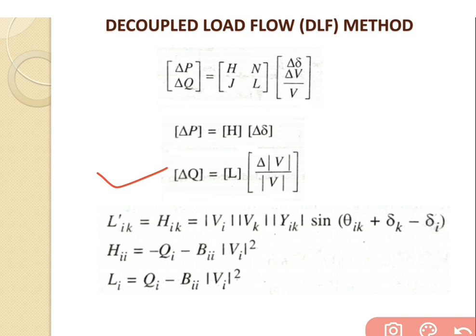The equation for power studies using Newton-Raphson method, which we have already obtained, is written as delta P and delta Q equals H, N, J, L into delta delta and delta V by V. The fast decoupled load flow method can be used for solving load flow analysis problems inside the power system, where H, N, J and L are the elements of the Jacobian matrix that we already derived in the Newton-Raphson method. The first step in applying the decoupling principle is to remove N and J, because these two elements are small. So we get delta P equals H delta delta, and delta Q equals L delta V by V.